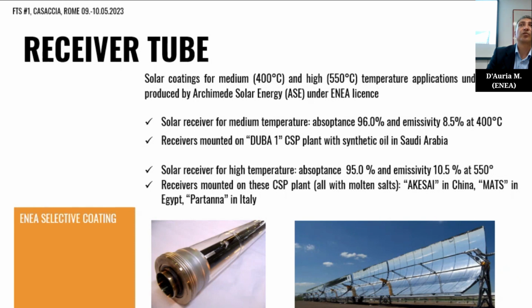So are there any developments in carbon steel for receiver tubes? So is it enough to use carbon steel coating or manufacturing the receiver, or are we always obliged to use stainless steel tubes? Okay, I repeat the question also for the online participant. So the carbon steel is used only for oil. We have no experience in these topics. So with the ternary salt, it is suggested to use stainless steel, for example AISI 316, but not carbon steel.